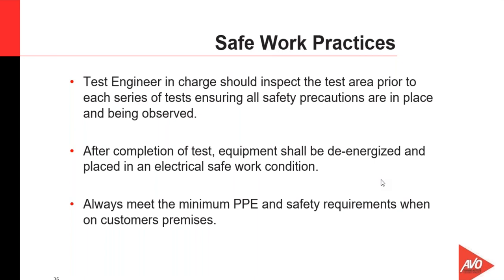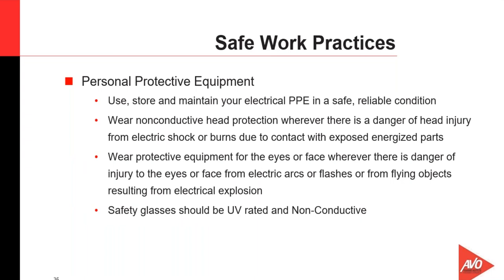Always meet minimum PPE and safety requirements on customers' premises when performing high voltage and high current testing. All personal protective equipment items have in-service care and use programs. These programs dictate that the PPE be inspected properly, be stored properly, be worn properly, and have proper fit. Always wear E or G rated hard hats or head protection, and wear protective equipment for the eyes and face. If there's any danger of arc flashes or flashes from flying objects or anything like that, then certainly we would wear face protection. Face protection may be a face shield, an ultraviolet rated face shield.